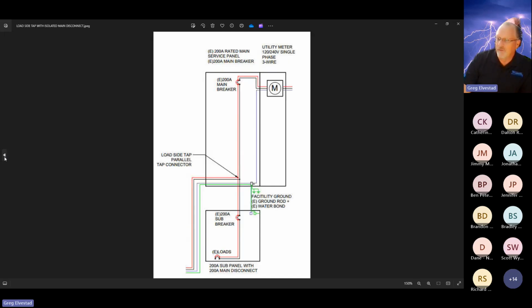And moving now to load side. Why is it load side? The thing to look at is where's your meter? Follow that to the distribution capabilities in the dwelling. Are you going to encounter an overcurrent device? Yes, a main breaker. If that exists, you're on the load side connecting to the dwelling.